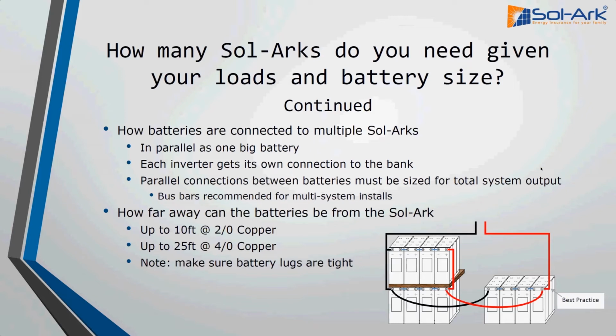Another thing to consider: how far can you put the batteries from the system? The usual answer is about 10 feet if you use 2-aught copper wire. If you buy the wire from us directly, we give you a 6-foot stretch of 2-aught copper wire, that's our standard length. You can go up to 10 feet with 2-aught, and up to 25 feet with 4-aught. Anything further than that gets pretty rough for a 48-volt battery bank, so it is what it is if you have to, but make sure you do the math on that.